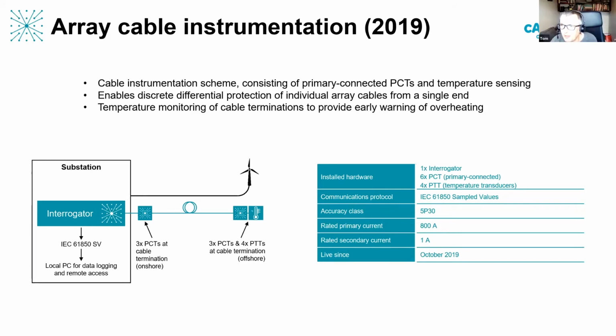Definitely cable terminations. It's a real problem area for the industry. And on top of that, it seems to have lacked very much monitoring because it's so hard to do monitoring of those. So it's been interesting for us to be able to put these spot temperature measurements on cable terminations, because it will tell you instantly what the exact temperature at that location is. Whereas other solutions such as DTS have their place where they're very useful, but they don't tell you the spot temperature of the termination, and that's what we achieve here. And we also have a fourth temperature measurement just to give you the ambient temperature, which could be useful as well. So that's what we've deployed here.